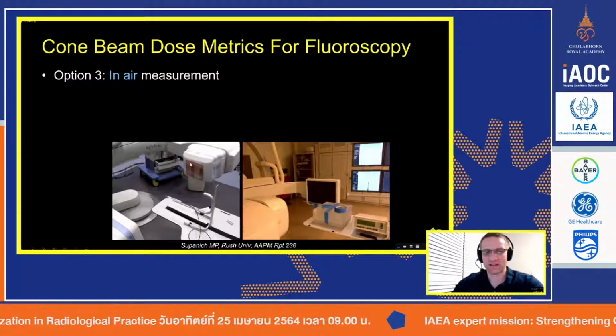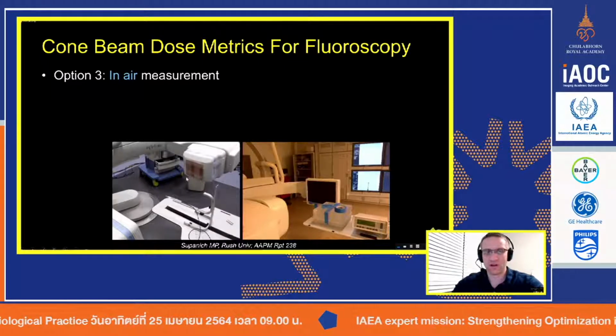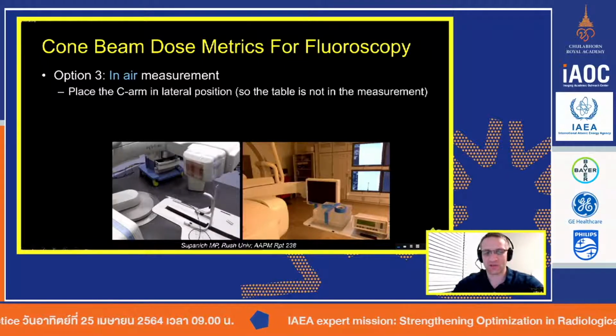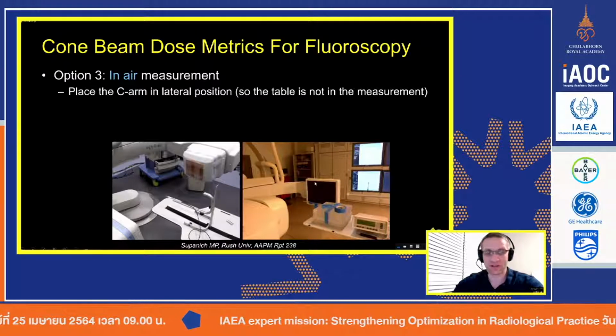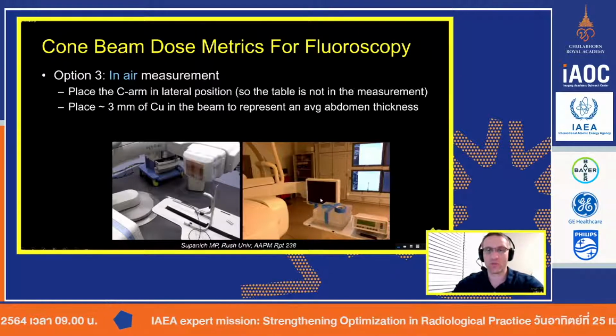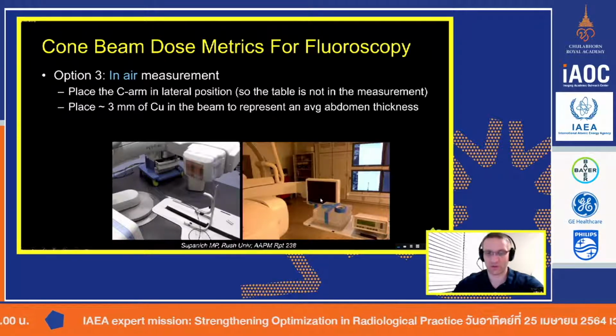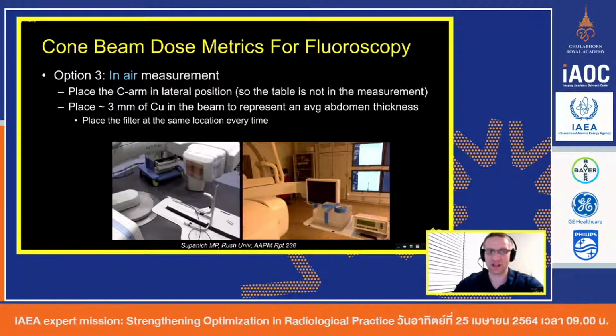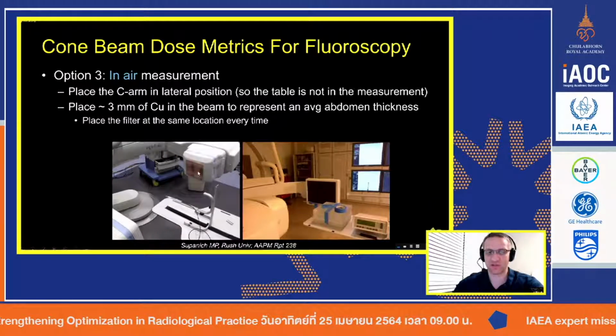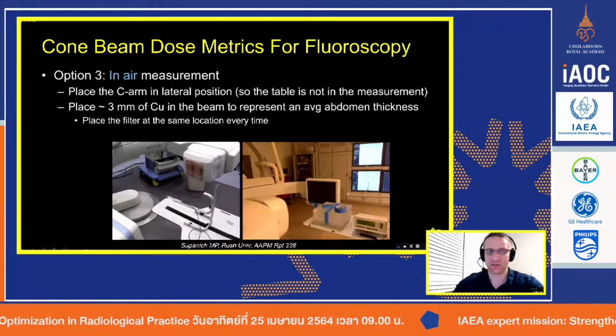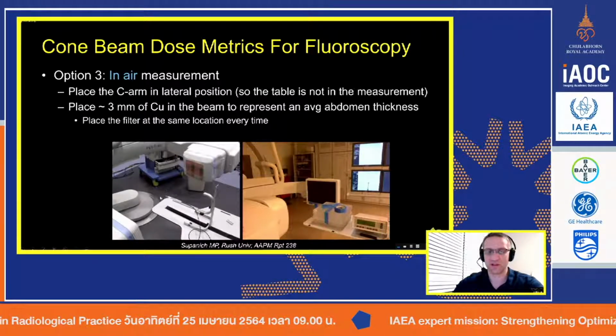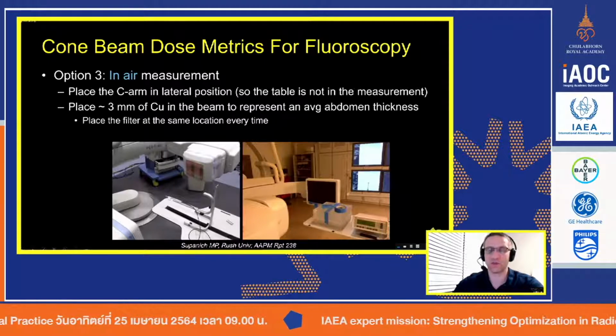You're going to place some kind of filter. You either place it on the X-ray tube side or you put it on the detector side. Where you put it is very, very important. You have to be consistent every time. Because if you put it on the X-ray tube side, when the photons come out, it reduces the beam, so the value you measure on the ion chamber is going to be low.